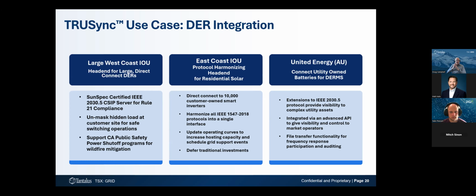We have another East Coast utility where the grid data management system is doing protocol harmonization in a head end for residential solar, direct connection to 10,000 customer-owned smart inverters, harmonizing data and doing protocol and data model translation across several IEEE 1547 protocols - in this case 2030.5, DNP, and Modbus - giving the ability to update operating curves. There's an ADMS system at the head end that only speaks DNP, and smart inverters out there speaking Modbus or 2030.5, with the grid data management system translating in between.